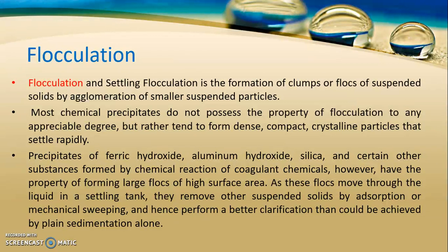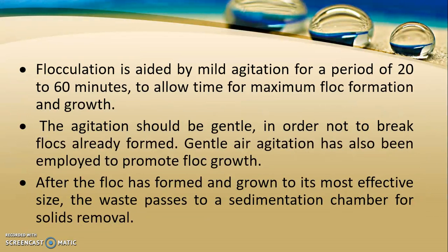As these flocs move through the liquid during settling, they remove other suspended solids by adsorption or mechanical sweeping, performing better clarification than plain sedimentation. When coagulants are added, they combine with the suspended colloidal impurities, destabilize them, form larger particles called flocs, and these flocs settle down. Flocculation is aided by mild agitation or mixing for a period of 20 to 60 minutes to allow time for maximum floc formation and growth. The agitation should be gentle so as not to break the flocs formed.